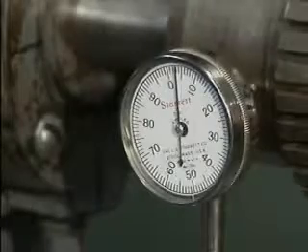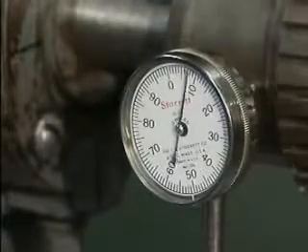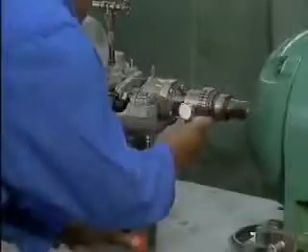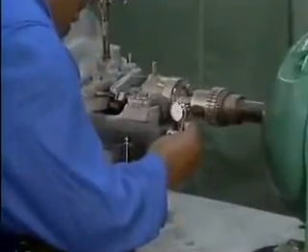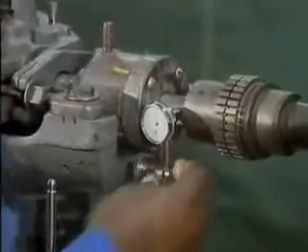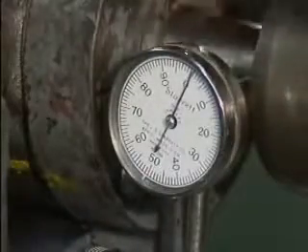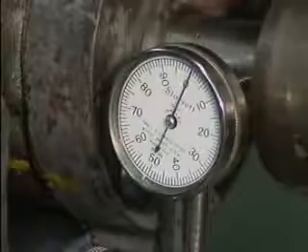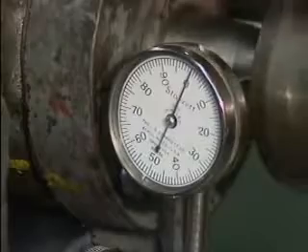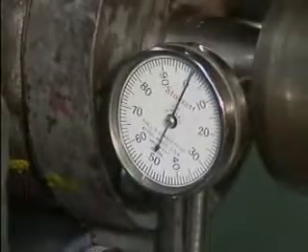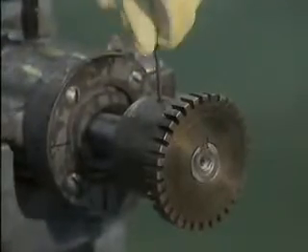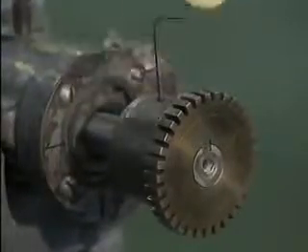Facilities generally specify the amount of run-out that's allowable. If readings exceed the allowable limit, the cause of the problem will need to be determined. One way to narrow down the cause of the problem is to take another set of run-out readings with the dial indicator stem contacting the shaft. If those readings are within the acceptable limits, the problem is likely to be a defective coupling hub. But if those readings are also excessive, it's likely that the bearings are bad or the shaft is defective. Whatever the problem, the necessary repairs will have to be made before an acceptable shaft alignment can be achieved.